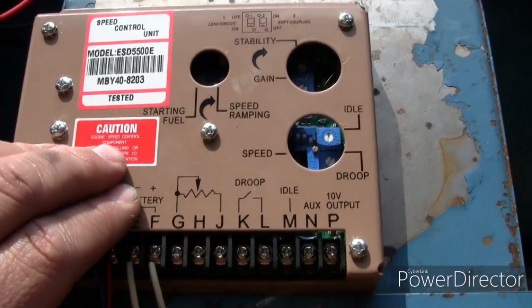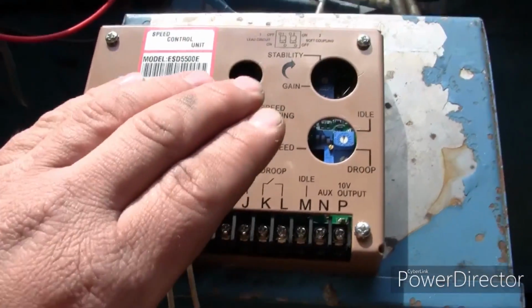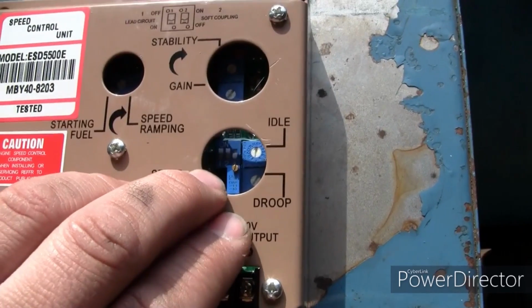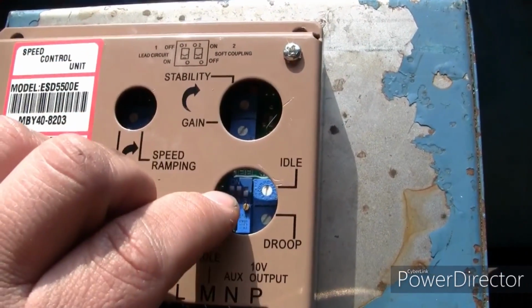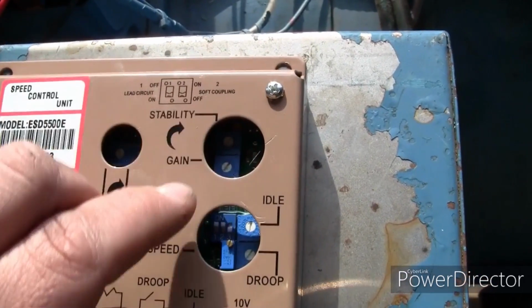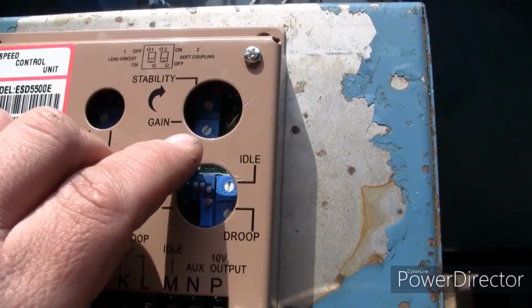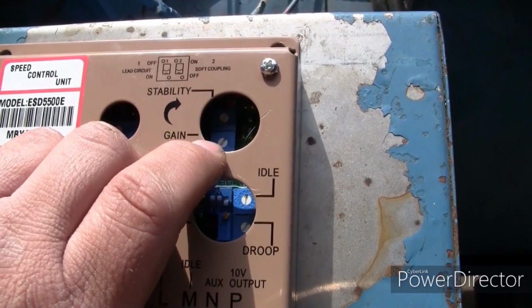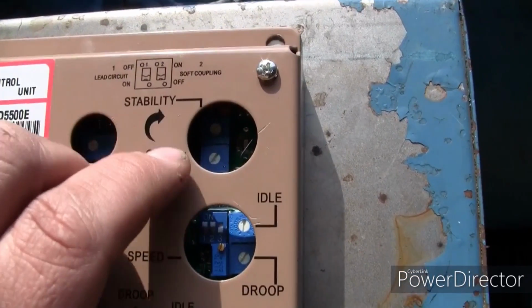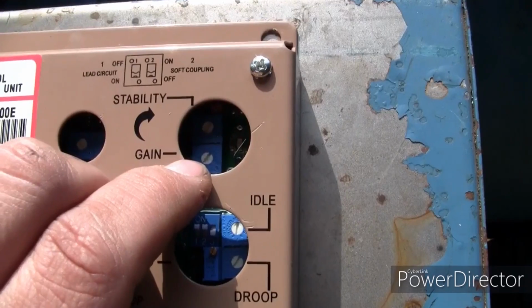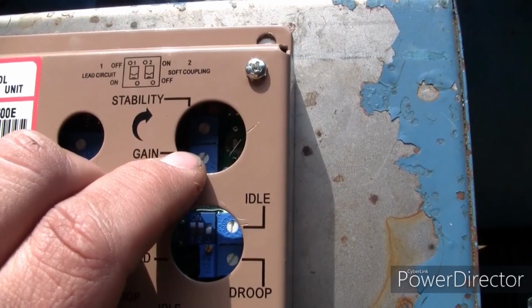Just pull up the manual for this and read about it. I have found that the best way to set these up is to set the lead circuit off, we don't need that, but to turn the soft coupling on. I usually start with setting both pots to either the middle position for gain and stability, or the minimum position. We're going to set these at the minimum.